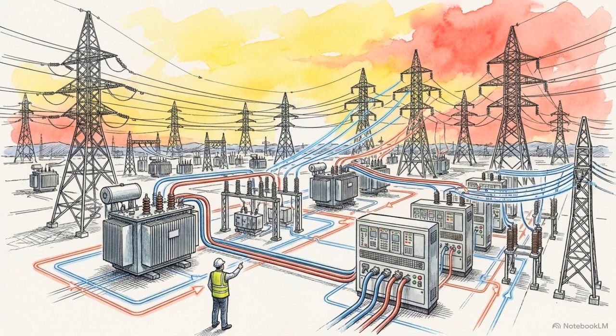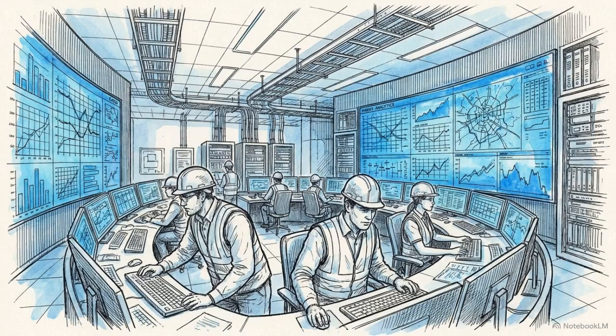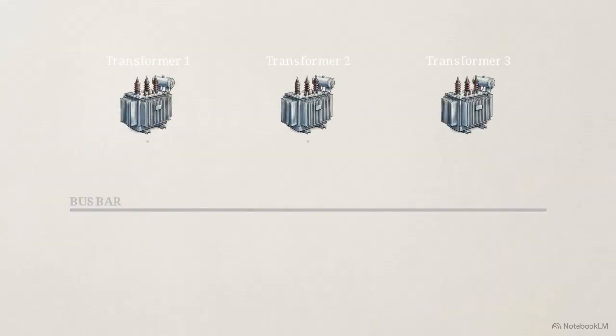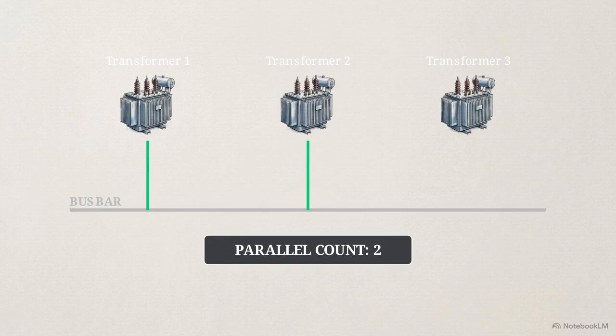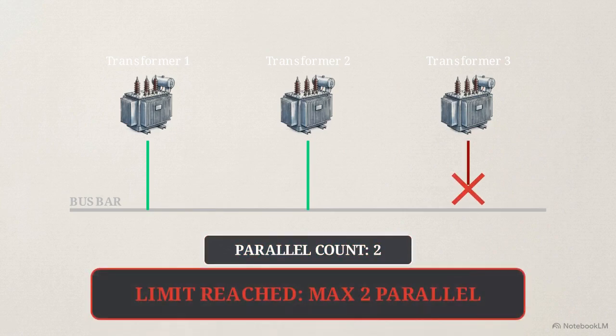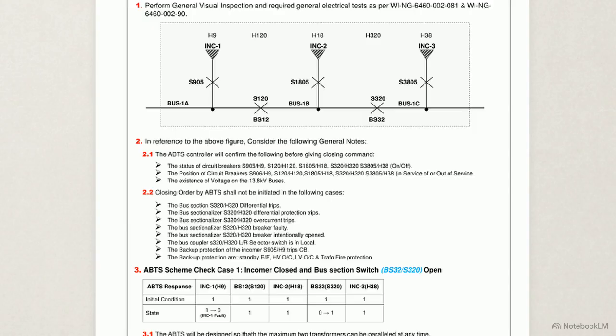the substation goes live. With the baseline secure, we enter the active control testing phase. We start with the Automatic Bus Transfer System, or ABTS. The central rule governing this system is strict. It must enforce parallel limits, which typically restrict the grid to a maximum of 2 parallel transformers at any given time. This ABTS check table and diagram detail Case 1.